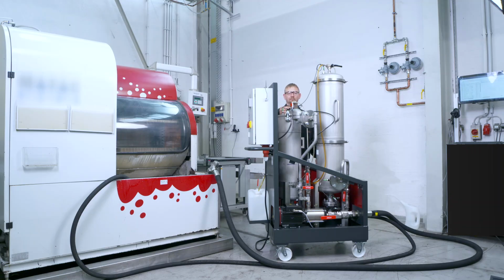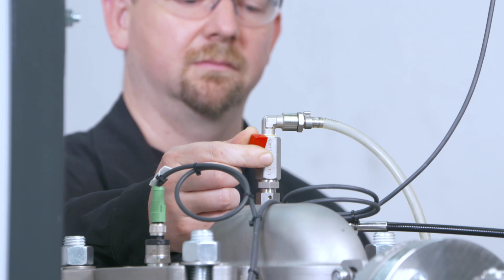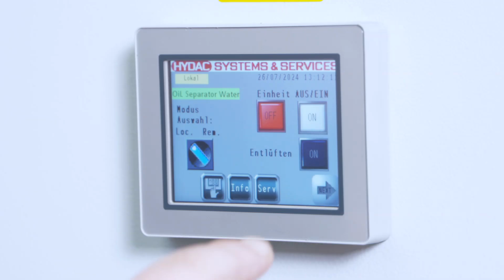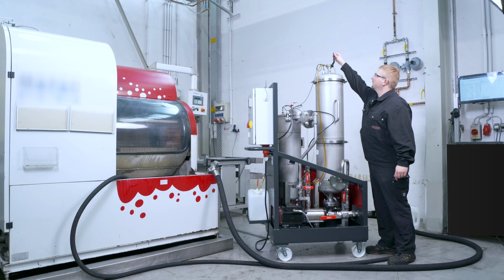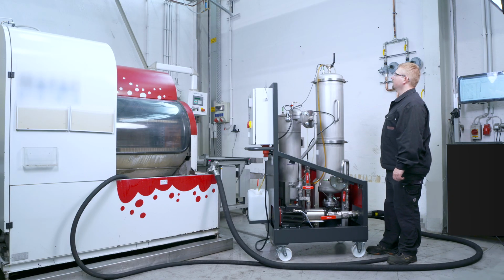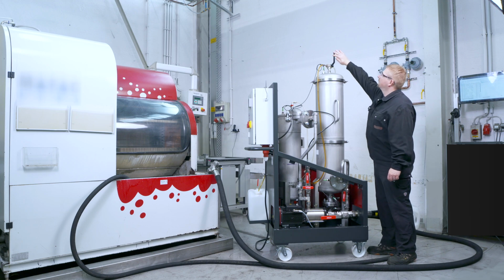The automatic venting of the OLSW always runs for 3 minutes. If the venting requires more time, then the process needs to be restarted. If the coalescence oil separator is not equipped with an automatic vent valve, then it must be vented manually.